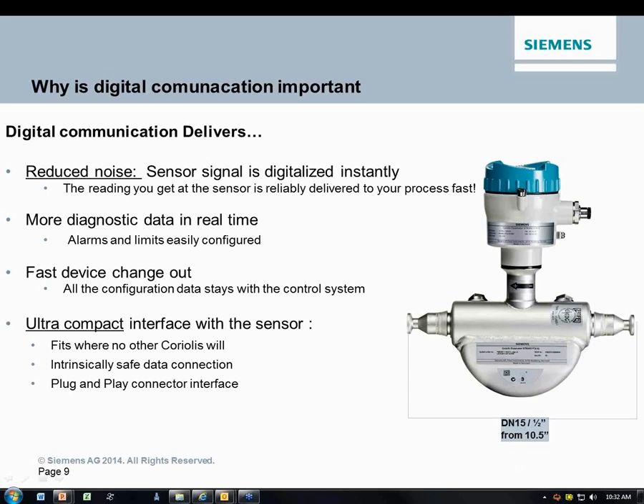Would you ever mount it horizontally so the tubes are horizontal? You mean basically so that the bump is facing the walls? So that this would be facing the walls? Oh, yeah. There'd be no reason not to do that. There's nothing holding you back from doing that. If you could only fit it in that position, the only consideration would be that you have two tubes in there, and if you're flowing a liquid, you would tend to have bubbles collecting in the upper tube.